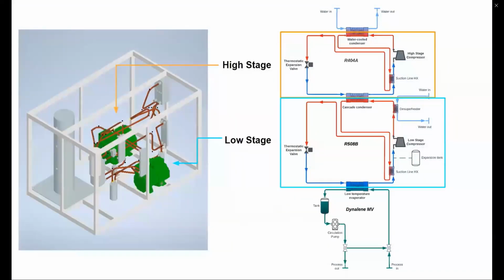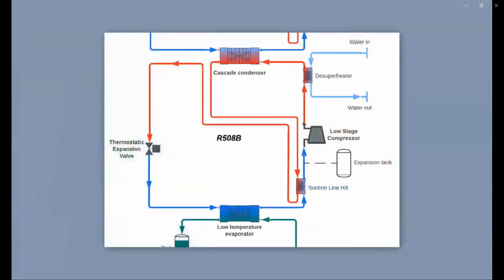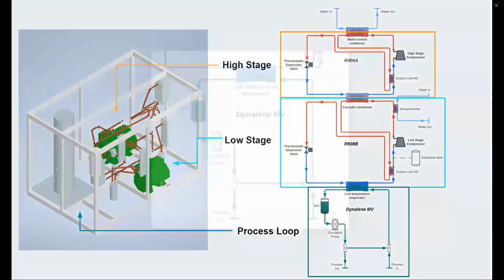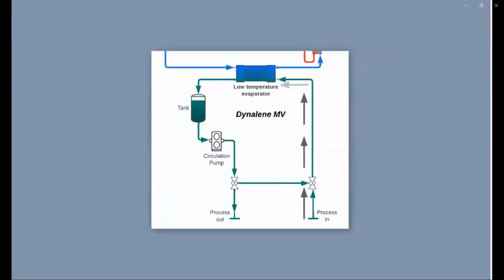Next, looking at the low stage, which is coupled to the high stage through the cascade condenser, key components include a suction line heat exchanger serving the same purpose, as well as a desuperheater, which reduces the thermal load on the high stage. Additionally, an expansion tank was added to limit the system pressure during shutdown to safe levels. Lastly, the process loop interfaces using the low temperature evaporator and simply circulates the chilled fluid, storing it in an insulated tank. Next, on to conclusions.